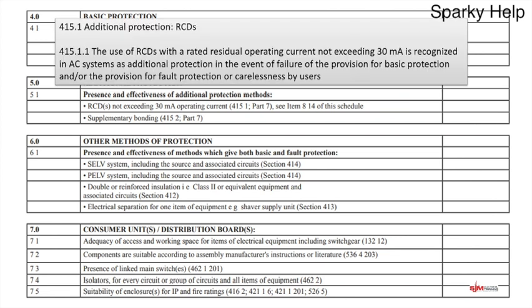Additional protection. To do additional protection, this is where we tend to put RCDs, because our regs drive us to do this. So this is for this reason, not the previous one. The use of an RCD not exceeding 30 milliamp is recognised in AC systems as additional protection in the event of failure of the provision of basic protection and any provision for fault protection, or carelessness by the user. So where have we done it? Have we put one in?